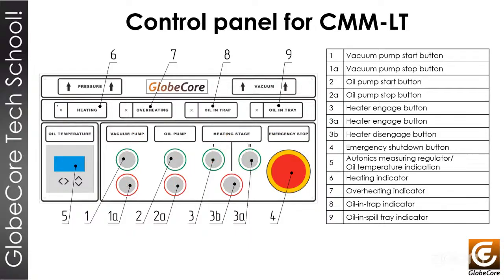Also, you will have different lights in the control panel. You will have a heating light that will turn on, of course, if the machine is heating the oil. Overheating: if the oil reaches a really high level of heating, the machine will tell you that maybe you have a problem and you had overheating of the oil inside the machine. You have the light of the oil trap. Remember, if the oil you are working with goes into the vacuum line, the oil trap will be activated and that light will turn on. The machine will have one alarm, and the oil-in-tray light will be activated when you have leakage in the machine and the machine detects that leakage. This light will turn on and the machine will give you one alarm, and you have to stop the procedure and review what is happening with the machine.